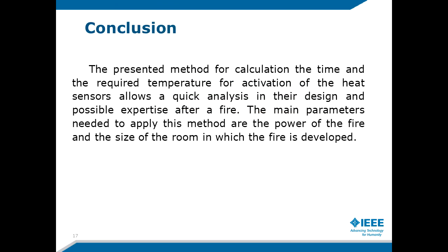The presented method for calculating the time and required temperature for activation of the heat sensors allows a quick analysis in their design and possible expertise after a fire. The main parameters required to apply this method are the power of the fire and the size of the room in which the fire is developed.